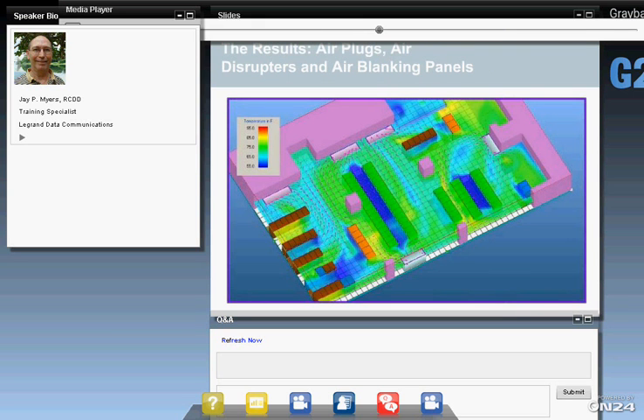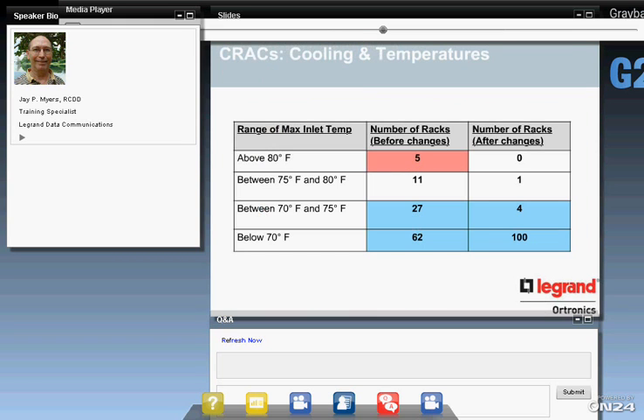Okay, so now we've taken these few steps, and you can see we've now gotten rid of that hot spot that we saw before. And now you see that dark blue in those aisles? That's way cold. That's a lot colder than they need to be. So according to our CFD analysis now, all the racks are below 80 degrees, so that's good. We only have 1 in the recommended range, and we have 100 that are colder than they need to be. So now what do we do here?